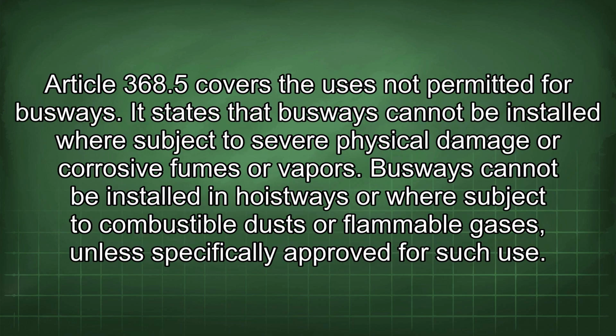Article 368.5 covers the uses not permitted for busways. It states that busways cannot be installed where subject to severe physical damage or corrosive fumes or vapors. Busways cannot be installed in hoistways or where subject to combustible dusts or flammable gases, unless specifically approved for such use.